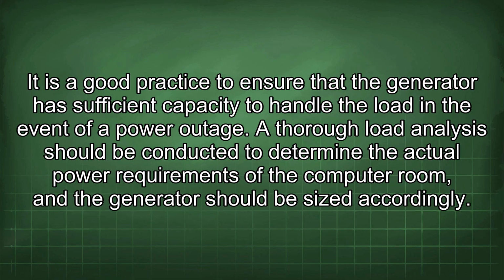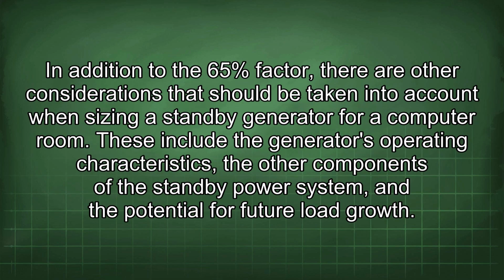It is a good practice to ensure that the generator has sufficient capacity to handle the load in the event of a power outage. A thorough load analysis should be conducted to determine the actual power requirements of the computer room, and the generator should be sized accordingly. In addition to the 65% factor, there are other considerations that should be taken into account when sizing a standby generator for a computer room.